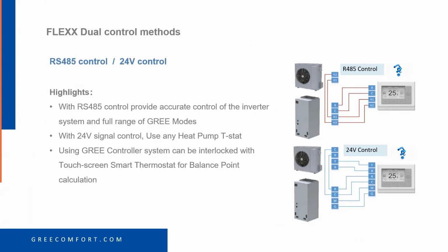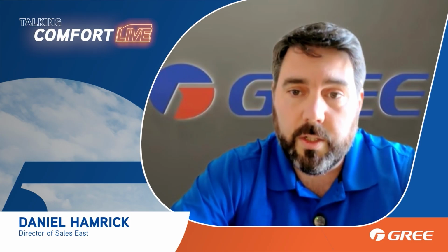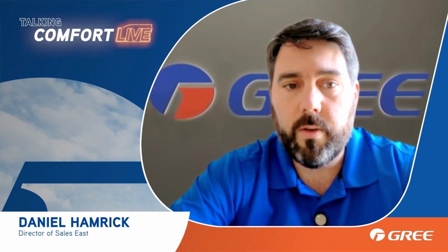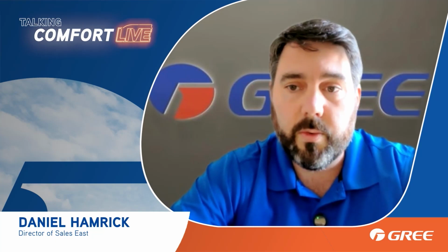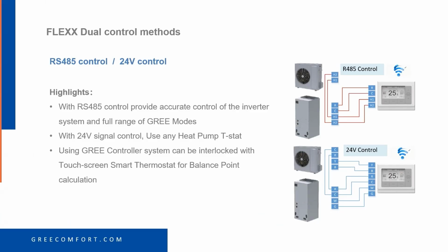So let's talk just a minute about how it can be controlled. We've done some testing on this, and Greg was kind enough to confirm this in Atlanta last week. So we do recommend go ahead and hook up the H1, H2 communication in between the indoor and outdoor, because what that's going to do is allow this thing to truly be an inverter instead of just using what the previous FLEXX used, which was a transducer to adjust that compressor and fan speed on the outdoor unit.